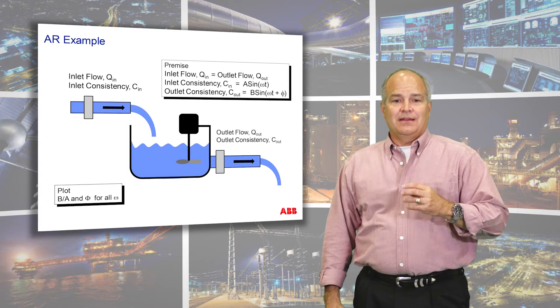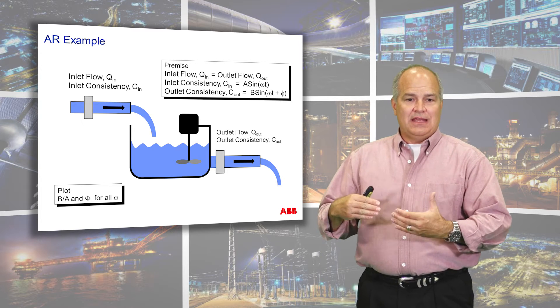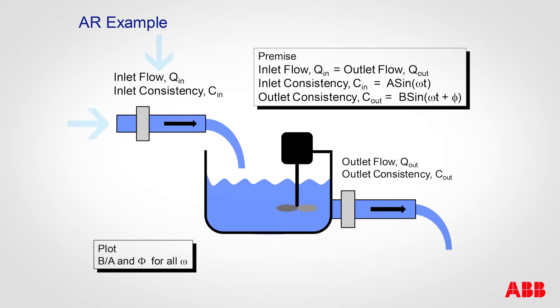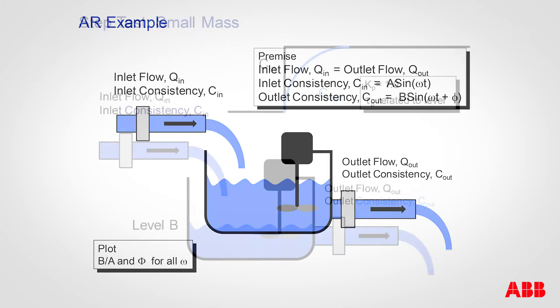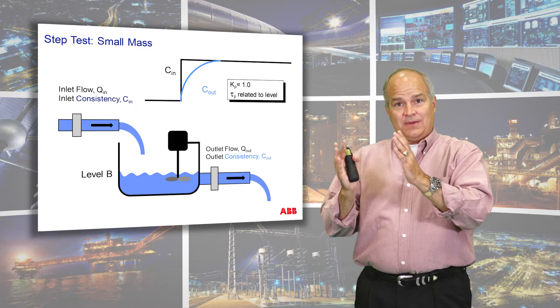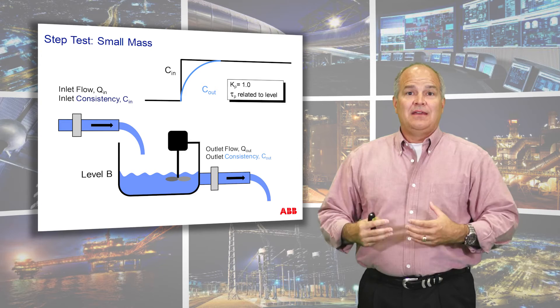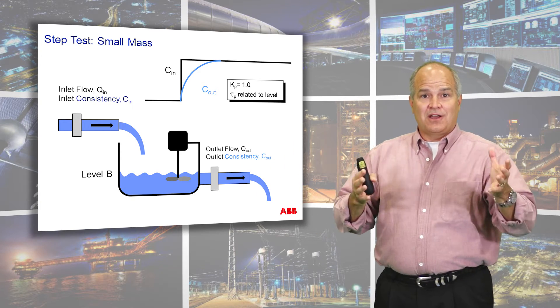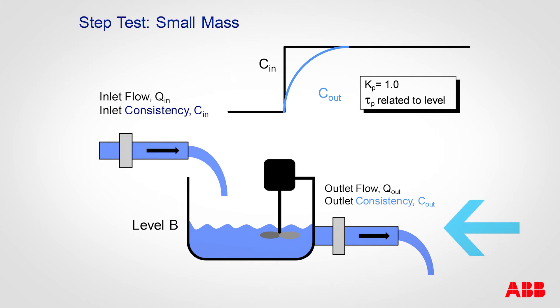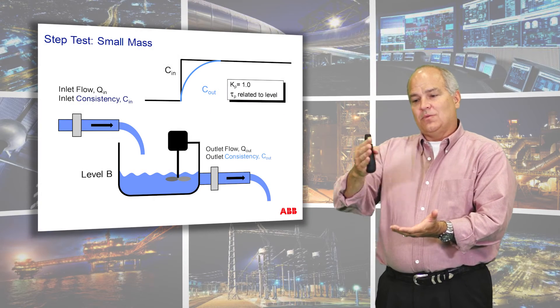This example is showing a tank that is well agitated, with a constant inlet and outlet. What we're doing is changing the concentration or consistency of the inlet. We let that reach equilibrium and then measure it on the output. What we're seeing is there should be a lag, and the lag is associated with the tank level. This is what we talked about in level tuning: if the tank is oscillating, this time constant is going back and forth, which is changing the frequency content that is passing through this mixing vessel.